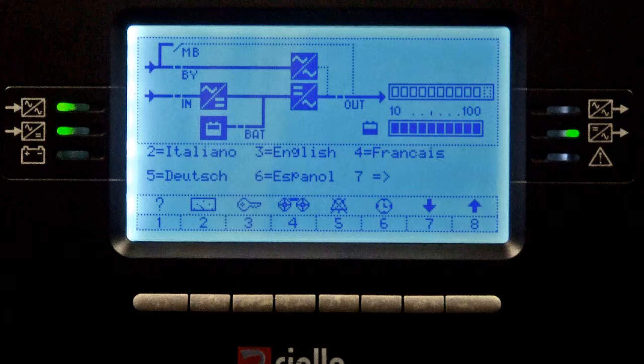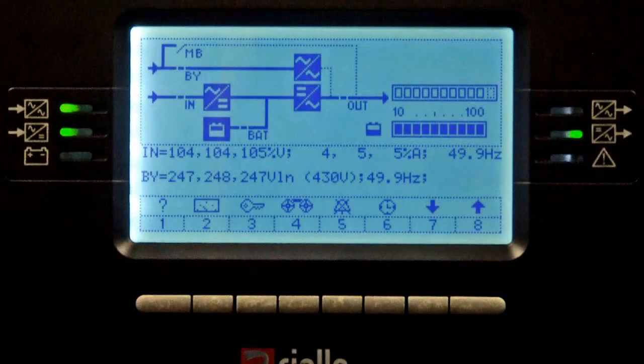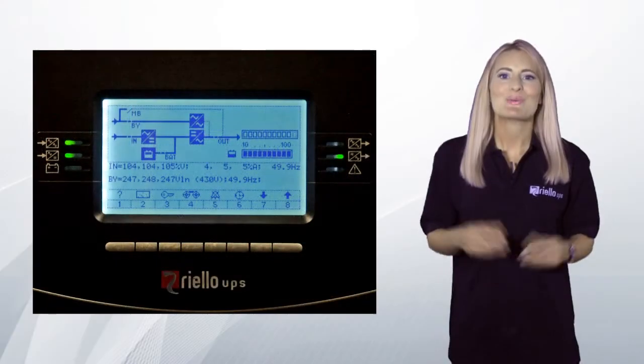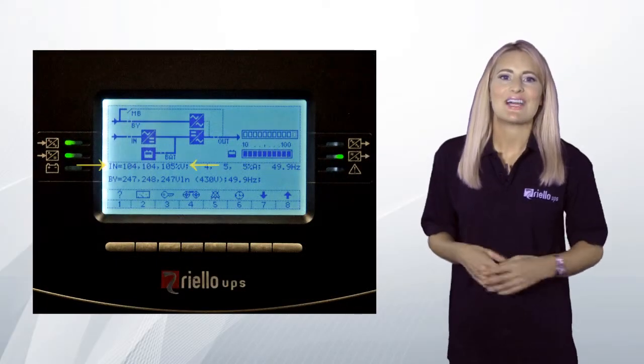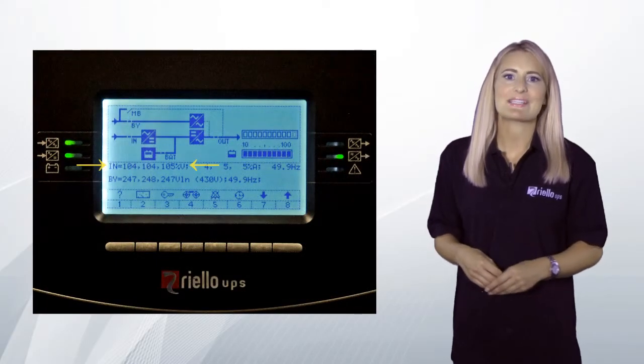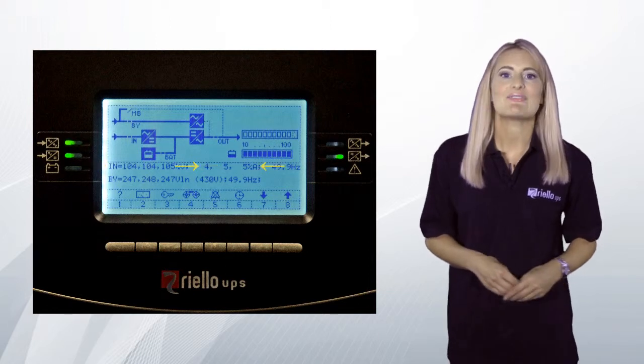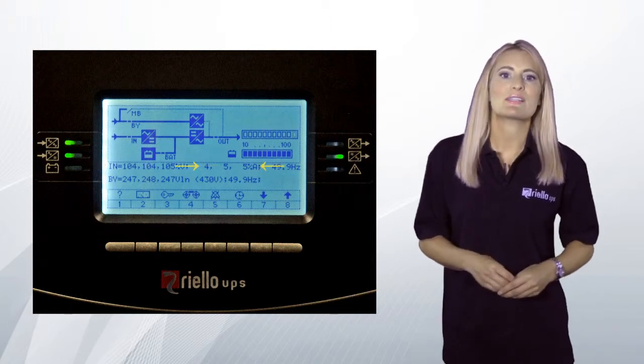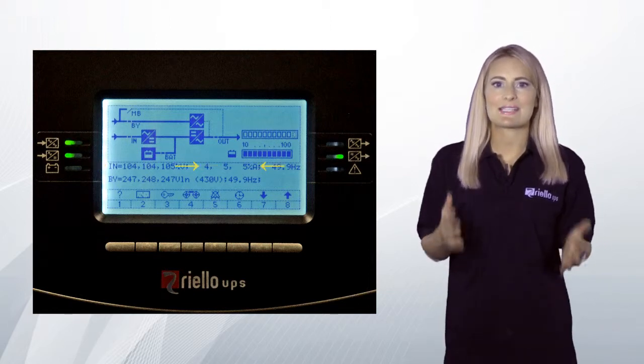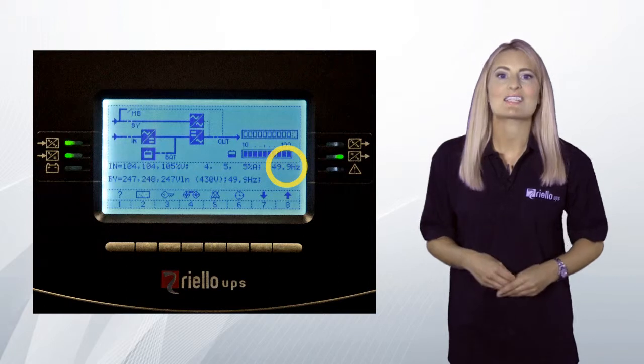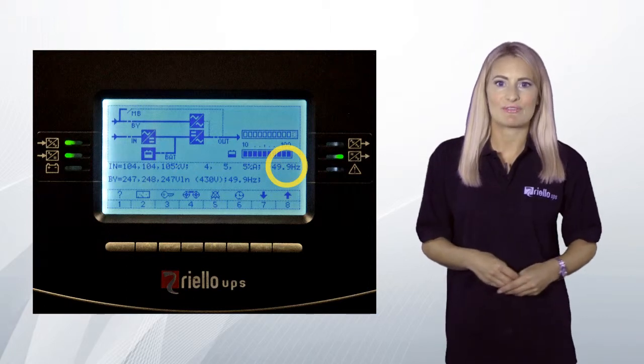From this screen, press button 8 to return to the main status screen. From the main screen, press button 2 to display the current UPS input parameters. You will see the rectifier input voltage displayed as a percentage of the nominal voltage, the rectifier input current displayed as a percentage of the nominal, and the rectifier input frequency.